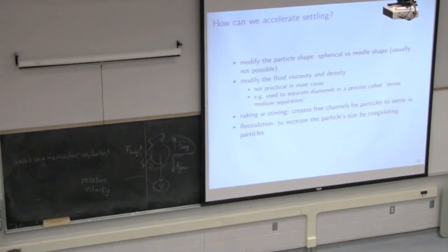Now, what we're most interested in is coming up with the size of these units that will work for the worst case situation. And the worst case situation is particles that are extremely small. The smaller those particles are, the slower they settle, and then the longer residence times we need, and longer residence times imply larger units. Larger units imply greater capital costs and larger operating costs.